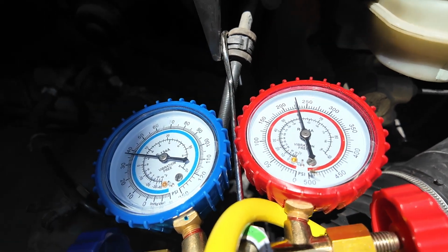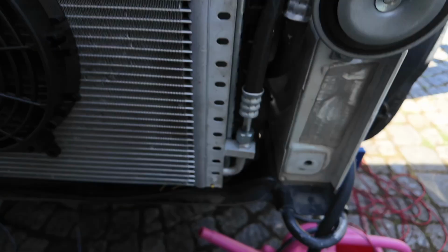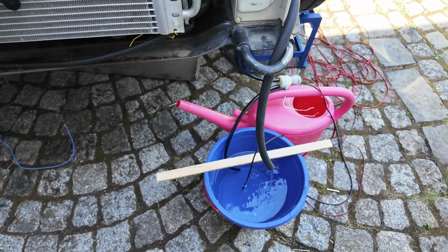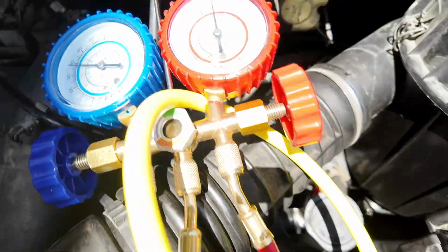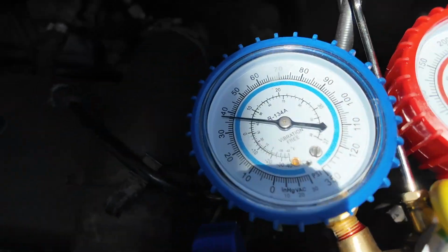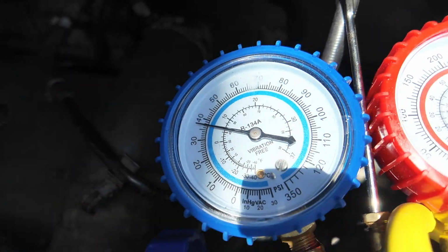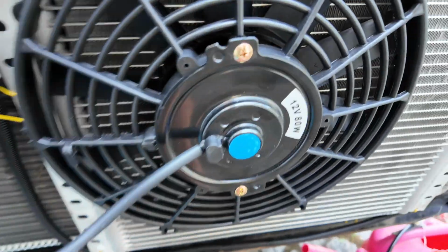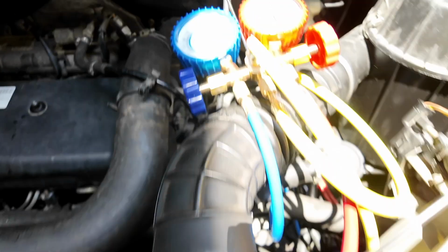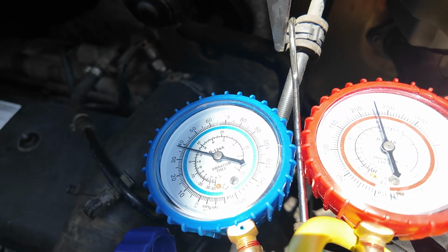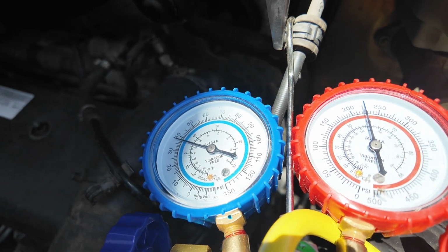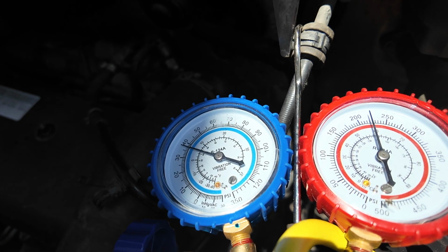So we try to run the system just on the heat exchanger. The water is still at 20 something degrees, but the high side pressure is getting out of range, high and low side pressure. So I need to kick in the fan, and that should drop now immediately.